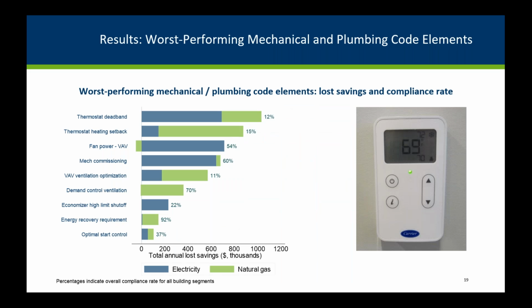Thank you, Jeanette. Let's take a look at the top worst performing elements in mechanical and plumbing end use. This chart shows code elements where we often saw non-compliance. The horizontal bars signify the total annual lost savings, broken out by fuel. Electricity is blue and natural gas is green. The percentages at the end of the bars show compliance rates for that measure across all building segments.